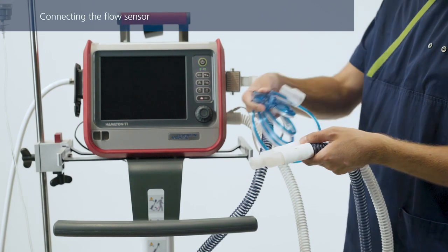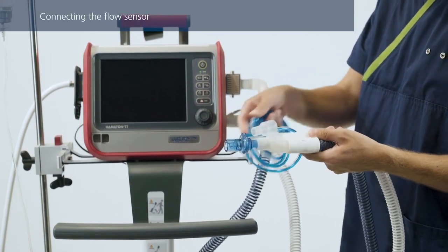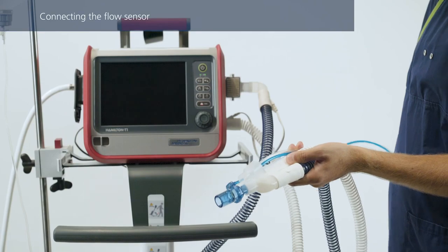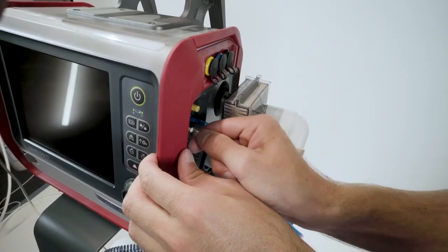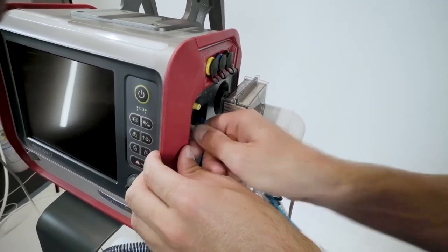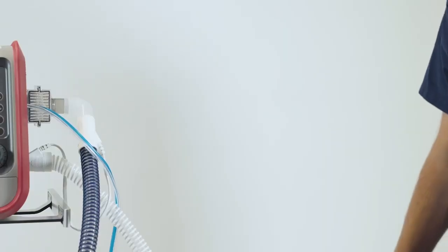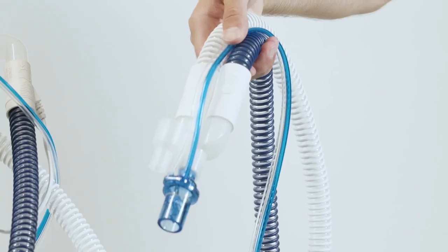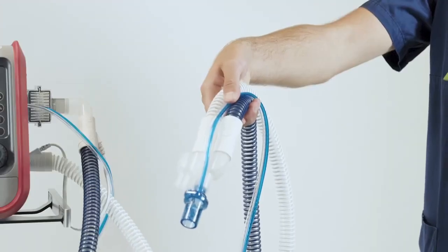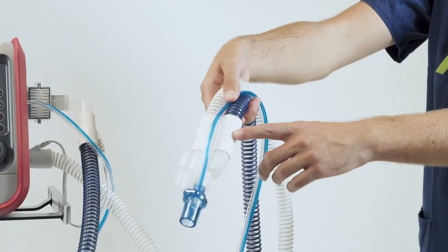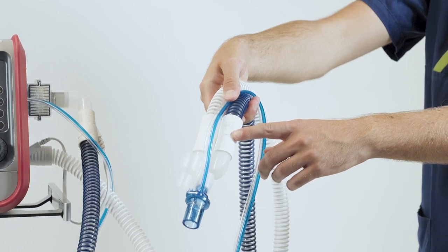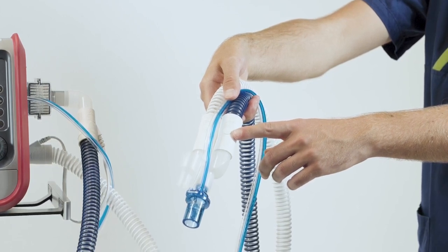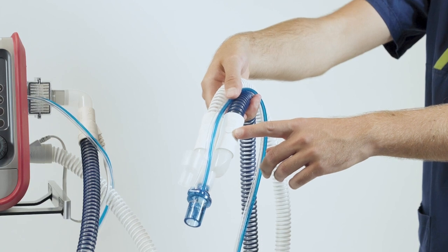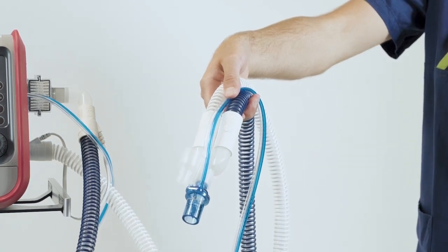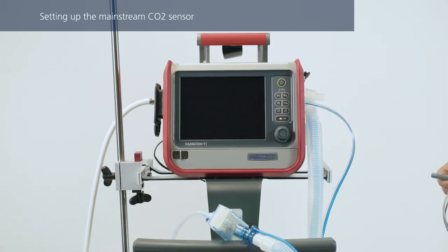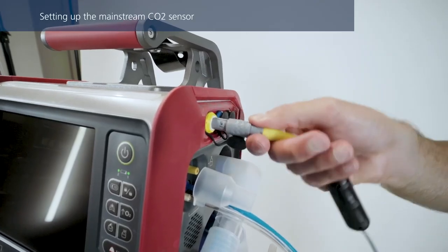Now you can insert a flow sensor into the breathing circuit in front of the patient connection, that is, the Y-piece. Then attach the blue and clear tubes to the flow sensor connection ports. To prevent water accumulating in the flow sensor and tubing, position the flow sensor tubing on top of the flow sensor. The gas temperature is measured at the Y-piece by the temperature probe integrated in the inspiratory limb. Make sure you keep the inspiratory limb positioned correctly.